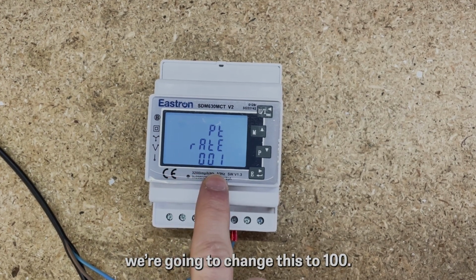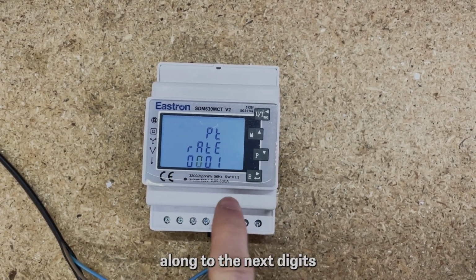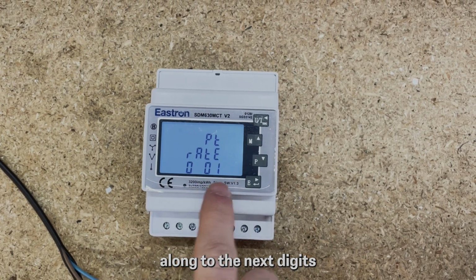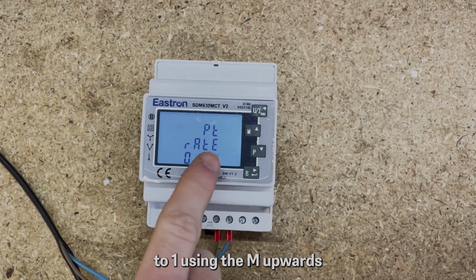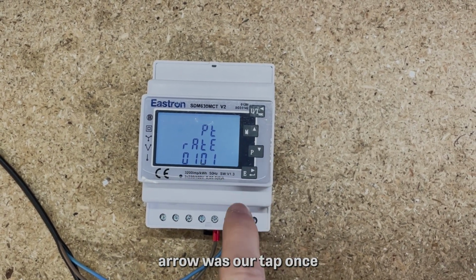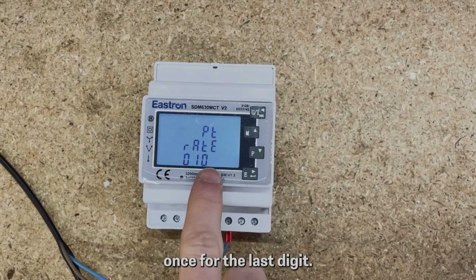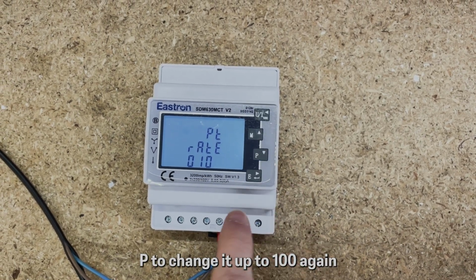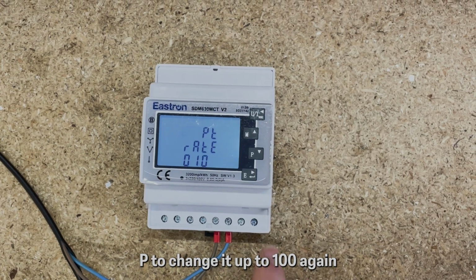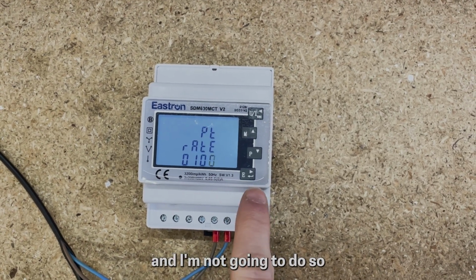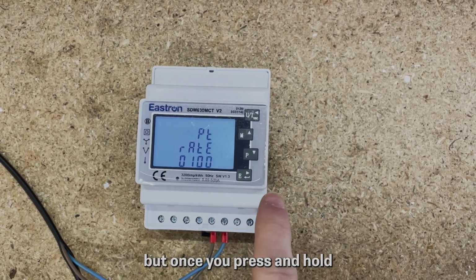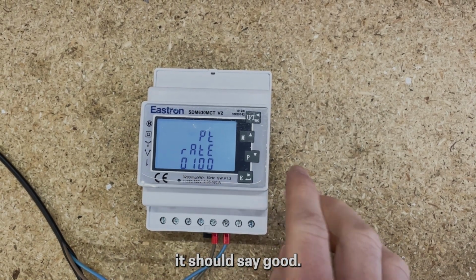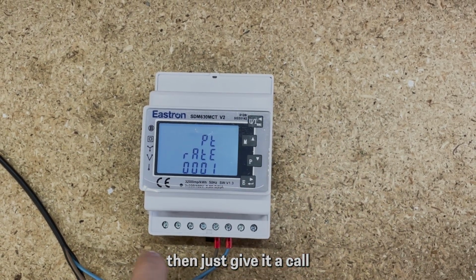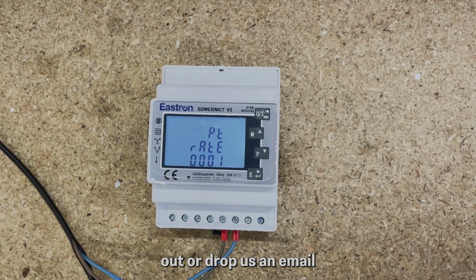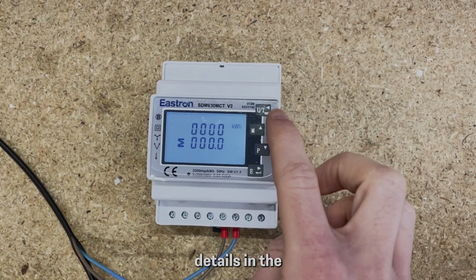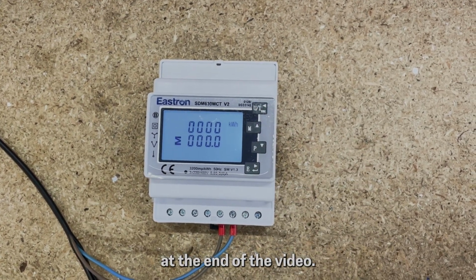We want to change this to 100. So I'm going to tap E to move along to the next digits. I'm going to change the 100 digit here to 1 using the M upwards arrow. Tap once, got to the last digit there, and we're going to tap P to change it to 100. Again, you'd press and hold E to save the setting. I'm not going to do so on this occasion, but once you press and hold E, it should say good. If it says error, then just give us a call and we'll be able to help you out, or drop us an email. I'll leave the details in the outro at the end of the video.